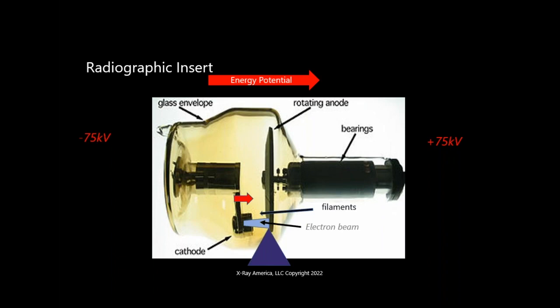Tremendous amount of heat. Now, why we use a rotating anode X-ray tube is because if this was a stationary anode and this didn't move, there'd be so much power going to this anode that it would actually heat through it. So these are made with tungsten, molybdenum, other alloys, and in the higher heat units, they're backed with graphite to take that heat. But the key is, heat has to radiate out. If you get too much heat through this rotor, you melt your bearings.